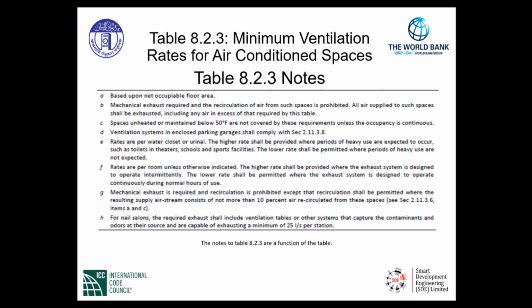For example, note H. Note H is given to us for nail salons. This is a specific requirement here, and it gives you a specific exhaust requirement in the ventilation table for nail stations such as tables or other systems that need to provide a source capture system. It means a local exhaust system capable of exhausting 25 liters per second per nail station. That's a specific note. And as you can see, all of the other notes are pretty important with respect to different areas within our buildings.